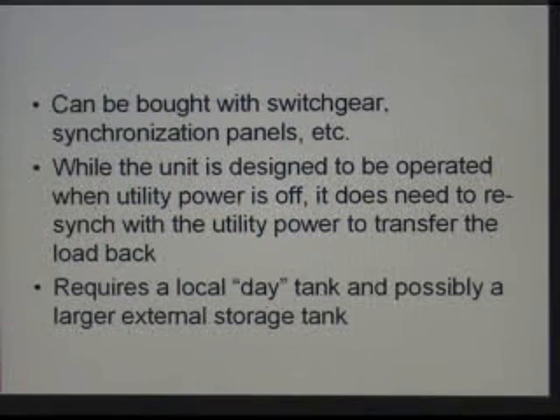And while the unit is designed to be operated when utility power is off, it does need to be resynced with the utility power to transfer the load back. Usually facilities are going to have what's known as an emergency bus, which has all of the important loads put onto it. And as soon as the utility power fails, there's a breaker that isolates that emergency bus from utility power. Well, the standby generator comes online and then powers that emergency bus. And they break that so that you're not asking the standby generator to power the whole rest of the facility. So now you've got your emergency system being powered by the genset.